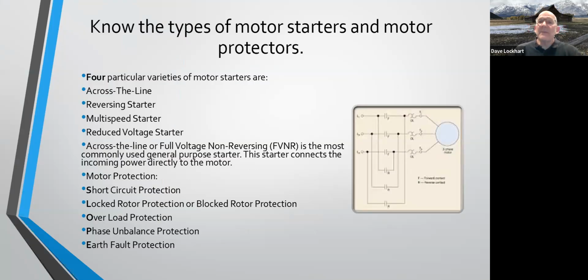Next question is, know the types of starters and motor protectors. So there are 4 particular varieties of motor starters. You got an across the line starter, you got a reversing starter, a multi-speed starter, and a reduced voltage starter. The across the line and full voltage non-reversing are the most commonly used general purpose starters. And the starter connects the incoming power directly to the motor load.